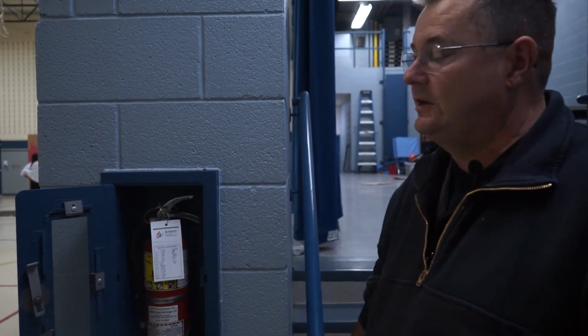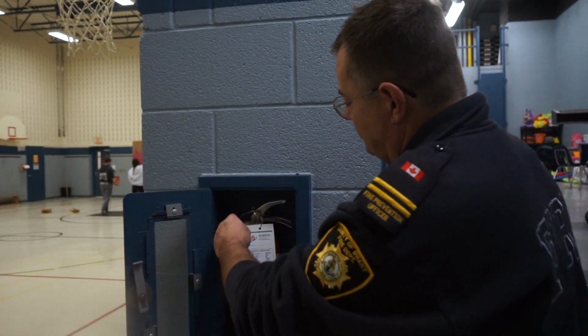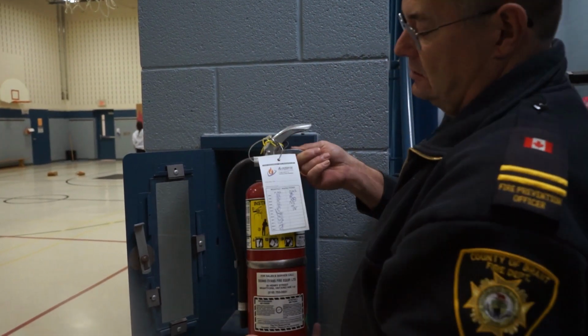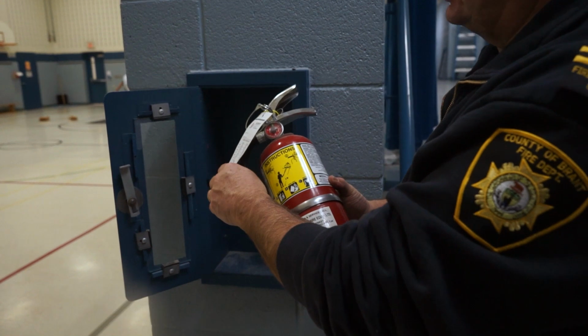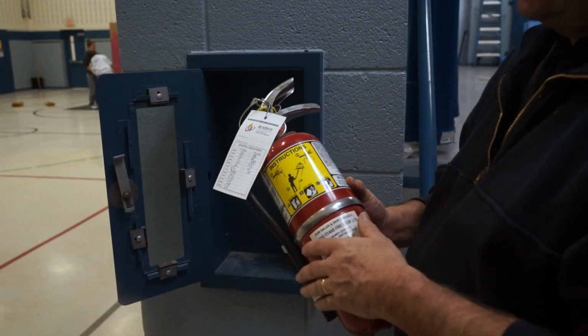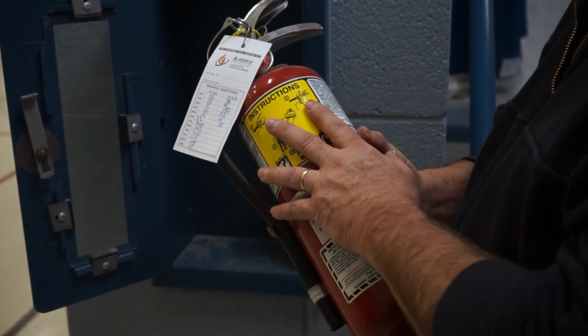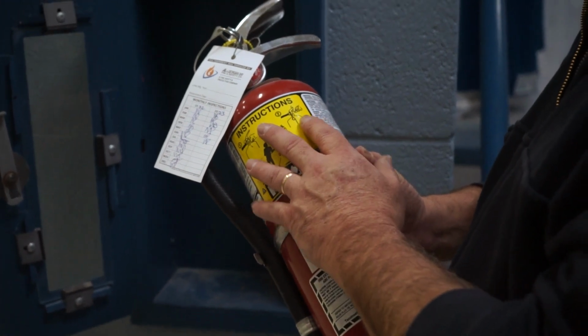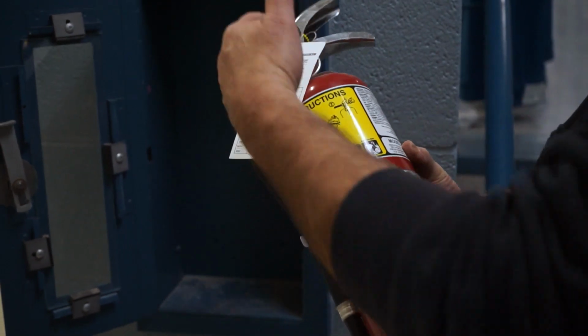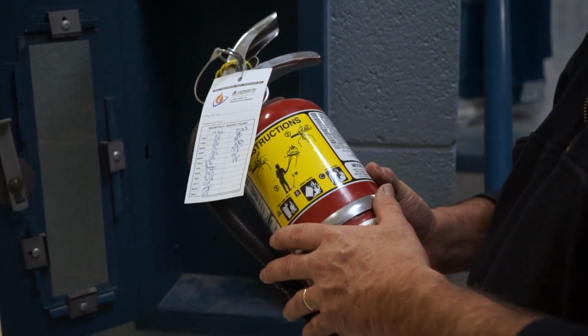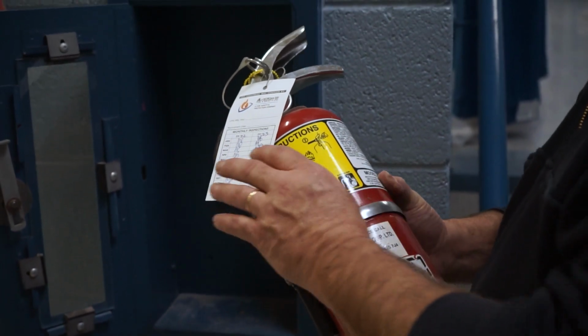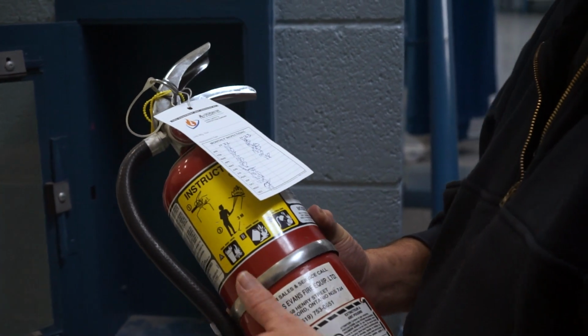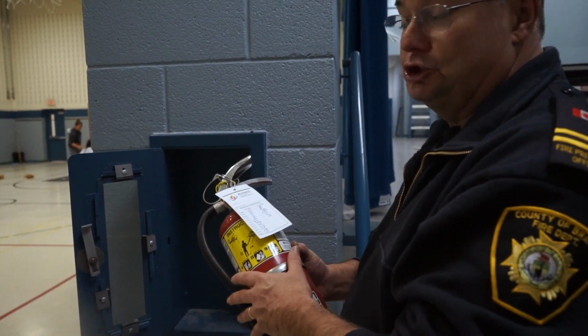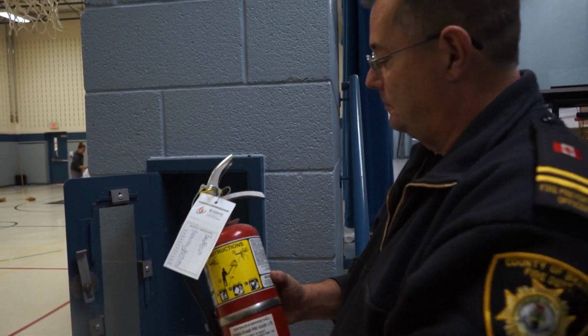One of the additional safety features that we find in almost every existing building is a portable fire extinguisher. Portable fire extinguishers, as well as sprinkler systems, as well as fire alarm systems, they're all a part of the fire safety chain. A portable fire extinguisher can be used if a small fire is discovered. As with the fire alarm and the sprinkler system, a fire extinguisher has to be maintained annually, has to be inspected monthly, and further to this, it is all part of the training that is provided to the staff, as everyone in the building should know how to use a fire extinguisher.